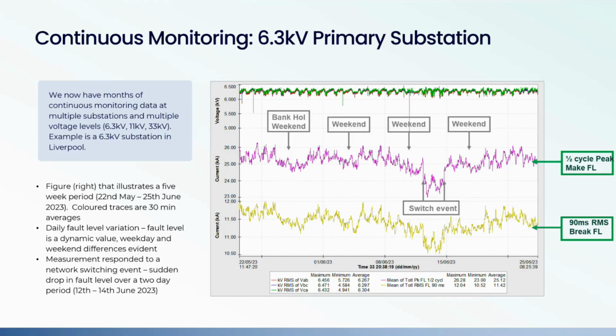And this site is a 6.3 kV primary substation, same one from the photograph earlier, in a city centre location. So we've got lots and lots of different things connected to our network in city centres. The interesting thing, as you can see from this trace, is a clear variability between daytime and nighttime in terms of the fault level, and also between weekdays and weekends. In fact, you can even see a slightly longer weekend where there was a bank holiday. So there are obviously some customers connected to the network in that area that are impacting fault level significantly during those times.